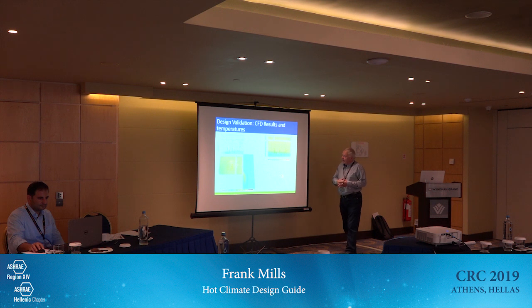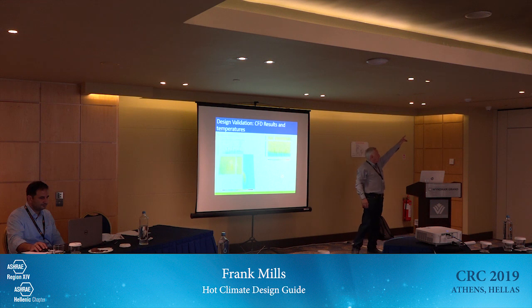I think one useful bit of feedback I would give you on this, one thing I learned, is you should control the air in and out. So if you take this as a room, for example, and the air's coming in, let's say under your window with some dampers there, that's great, and then it's going to go out, maybe through the ceiling, obviously not this ceiling, but an open grid ceiling, out to outside, and out there is an atrium. I did wonder whether you needed dampers here before you go out into the atrium.